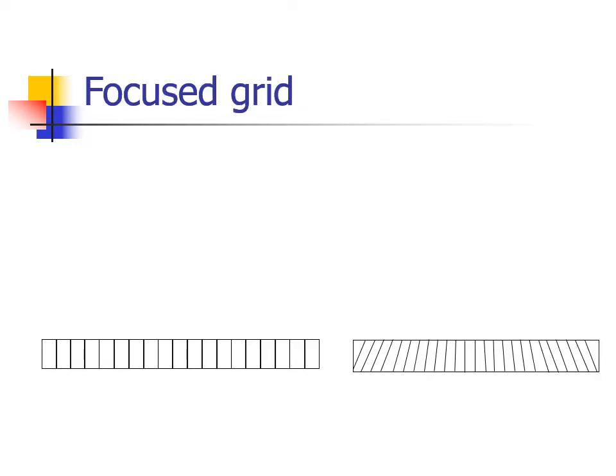On this slide, we have two grids. On the left is a familiar parallel grid, and on the right is what we call a focused grid. What makes a focused grid unique is as you move from the center of the grid, the lead strips are progressively angled to the center of the grid.